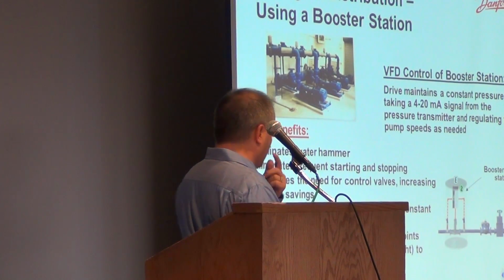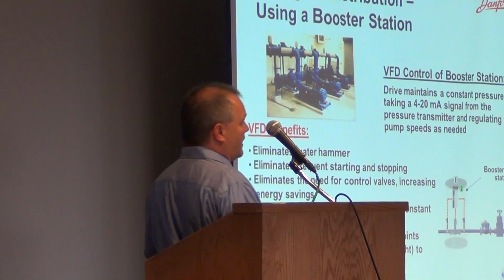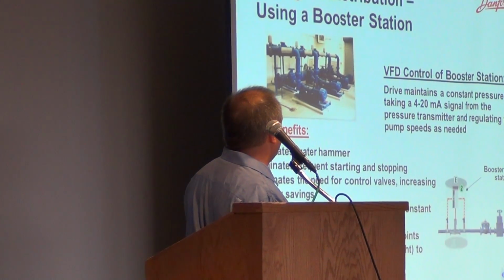We don't have any water hammer, which saves on pipe breakage. A lot of the older cities have the older pipes in the ground, and we've helped eliminate a lot of their pipe breaks by putting drives on their lift station pumps and on their city water pumps.